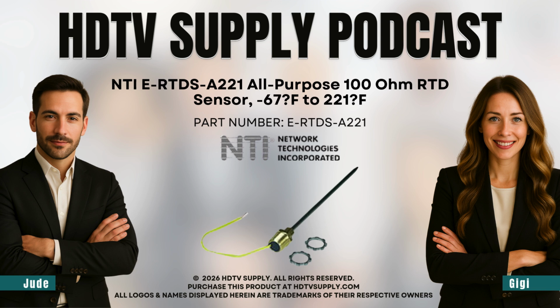Okay, but this is where I get a little confused. I saw that one of the compatible transmitters, the E-RTDS-1562, can handle temperatures up to like 1,562 degrees Fahrenheit. Yeah, it has a massive range. So hang on, if the electronics can handle these huge extremes, why are we paying $130 for a probe that maxes out at just 221 degrees Fahrenheit?